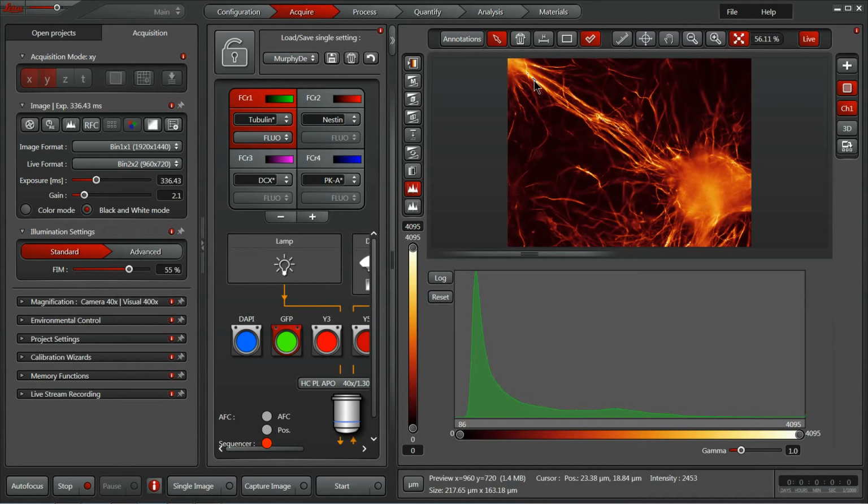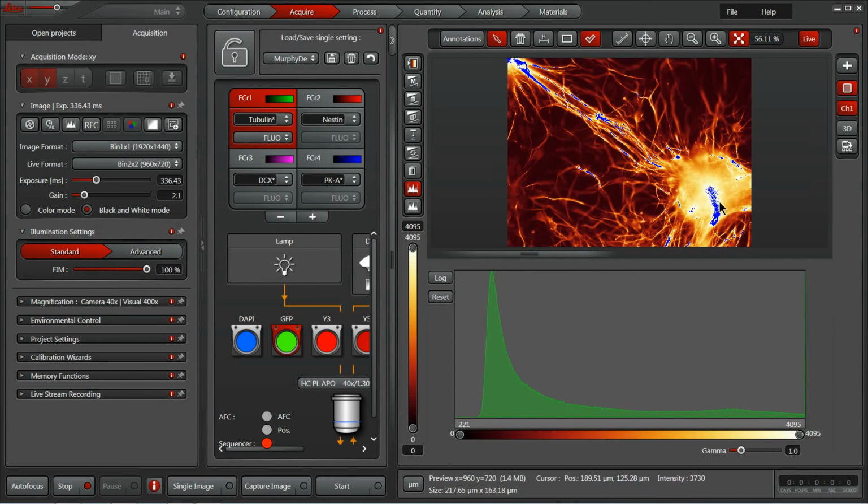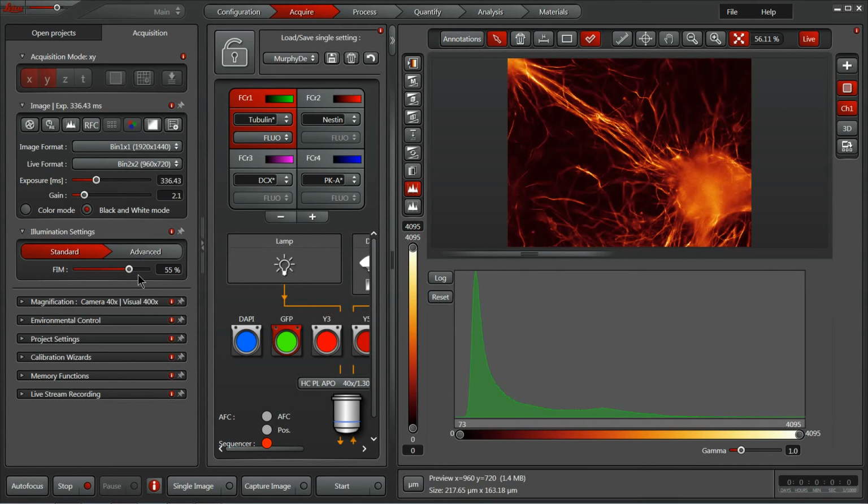And in this case, we also get this beautiful blue indicator of saturation. So if I maximize the number of photons going into the system, we see these huge areas displayed in blue are our saturated pixels, where the pixels are just overflowing with electrons. So we need to reduce our exposure time to get back within the range of the system, or equally, we can reduce the number of photons that are entering into the system.